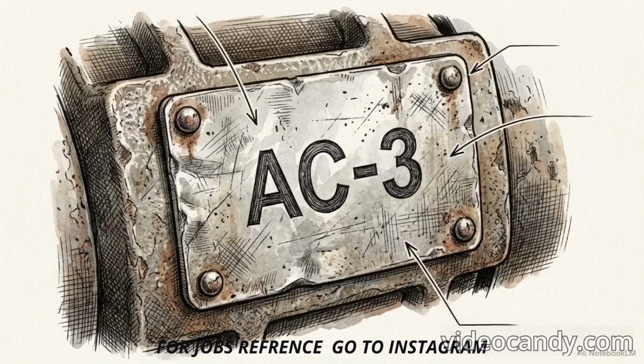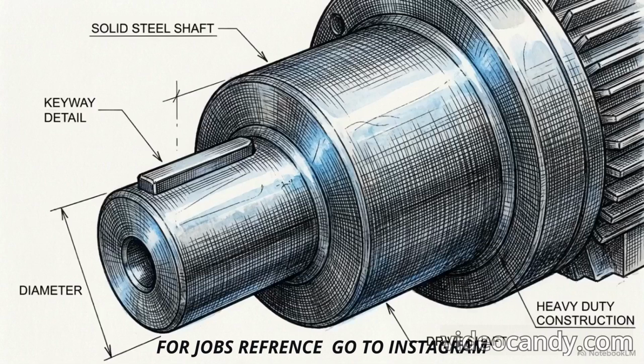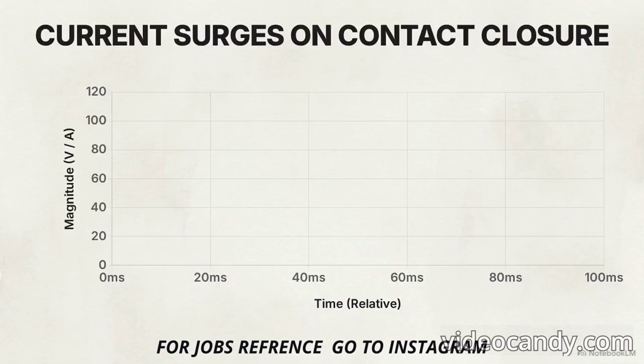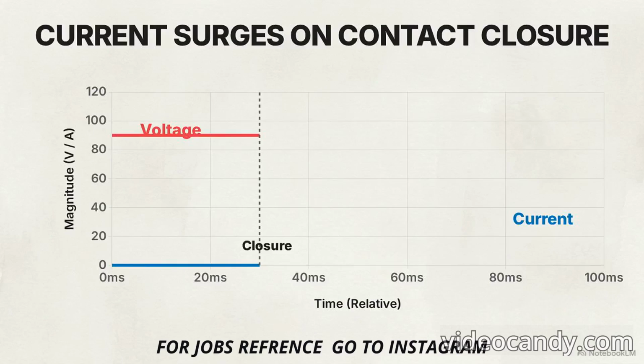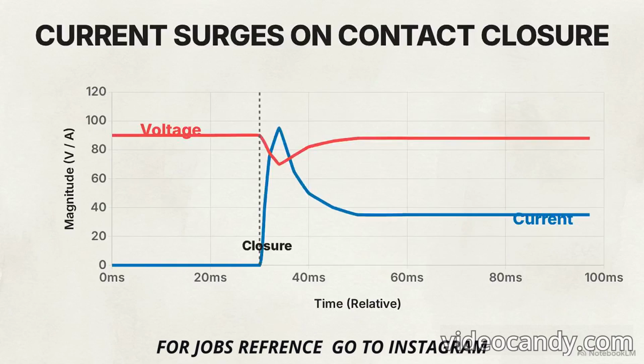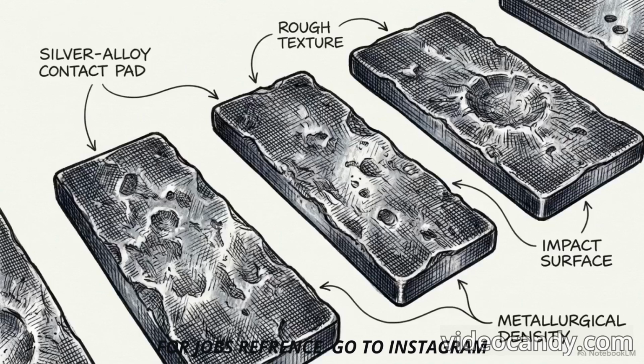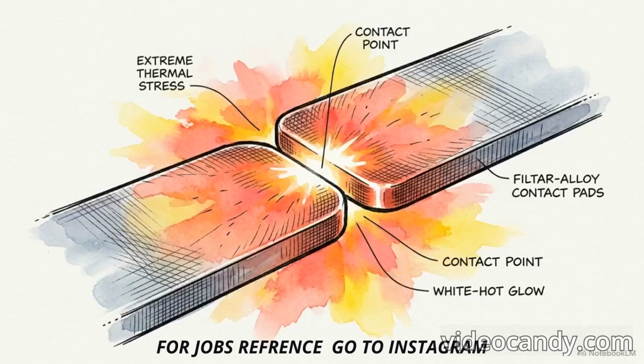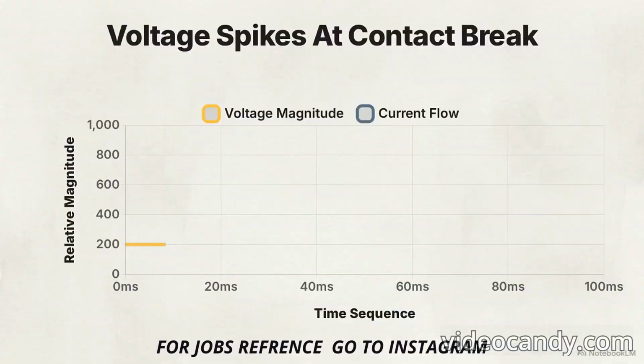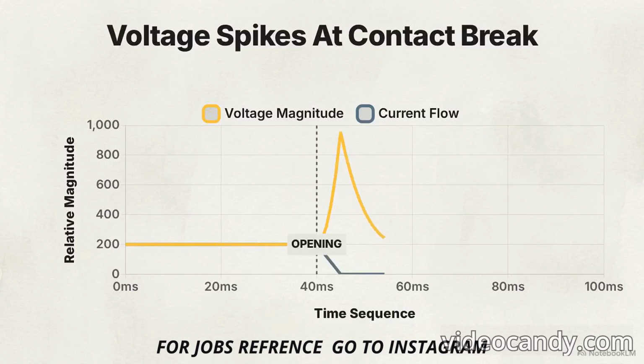Once mechanical closure is established, the contactor must survive the severe electrical physics of the AC3 utilization category, the specific dynamics of switching heavy inductive motor loads. This diagram maps the electrical dynamics during a standard closing event, tracking voltage in red and current in blue. At the exact moment of closure, you see a massive surge in the current line, alongside a slight dip in voltage. This is the making current. The contact metallurgy and the mechanical closing force of the armature must be robust enough to withstand this sudden thermal and electrical stress, without the poles micro-welding themselves together.